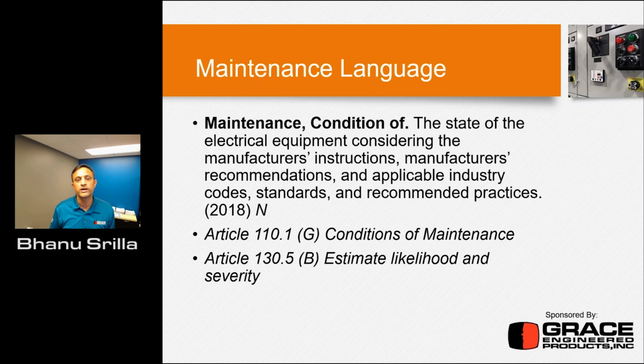And if you don't have those, then you can follow the consensus standards like NFPA 70B or ANSI NETA standards, right? And also industry guidelines per se. And then if you look at the next bullet, which is Article 110.1, conditions of maintenance has been called out even in that specific section within Article 110.1. And then when you look at 130.5, which is the estimate of likelihood and severity in the risk analysis of electrical hazards, you need to also take into consideration the condition of maintenance of that equipment itself. Not only the worker qualifications and installation guidelines, you need to take into consideration the maintenance condition of that specific piece of equipment too, okay?